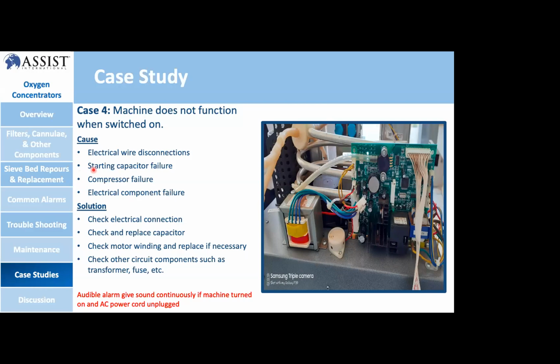The other one is compressor failure. The compressor may fail because the winding burns, or there may be disconnection of the power supplying cable to the compressor. And the other one is electrical component failure. For example, fuses, transformer and relay failure on the PCB board. We have a PCB board displayed on the right side, and we have a transformer, and we have a relay which controls solenoid valves. So if these two parts have failed, we replace those parts or take them from another equipment, and we fix the problem.